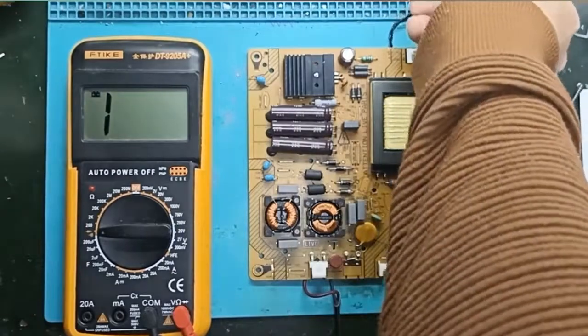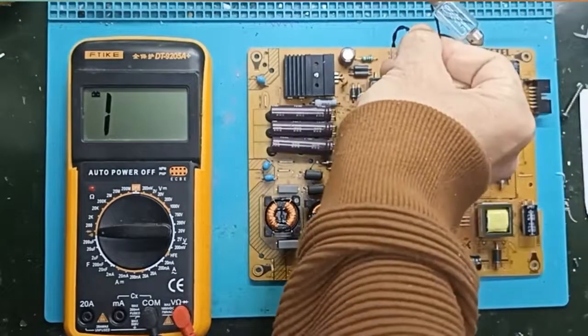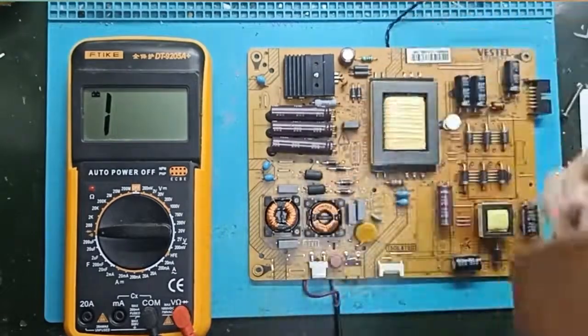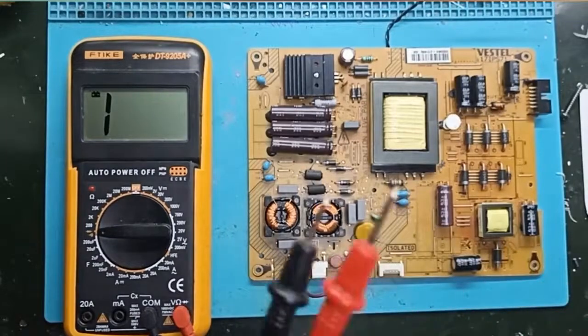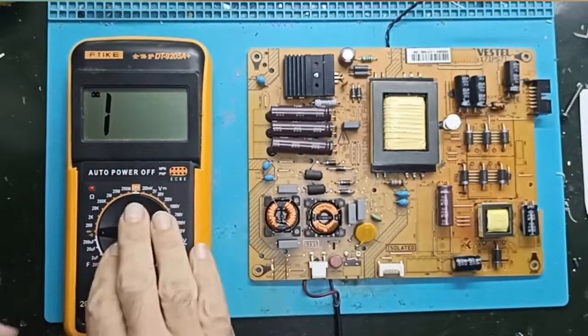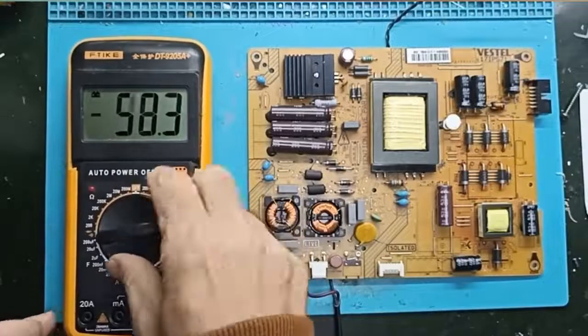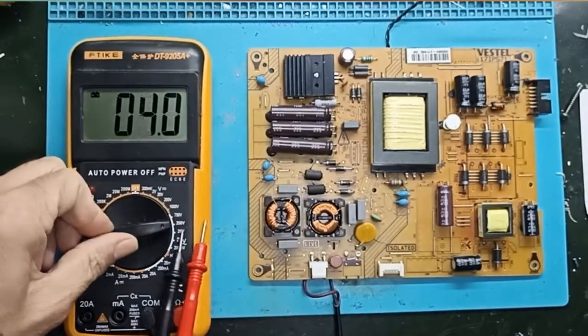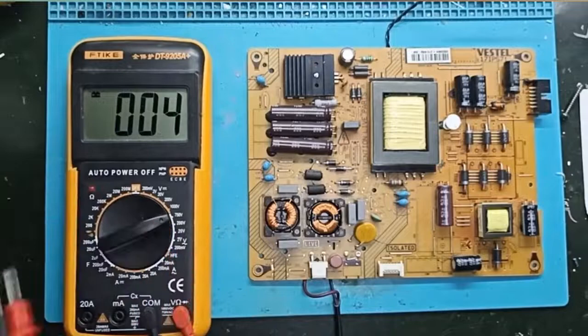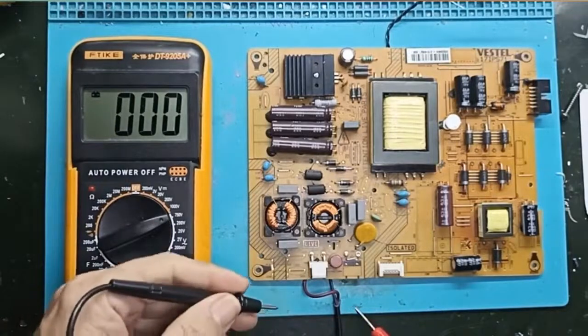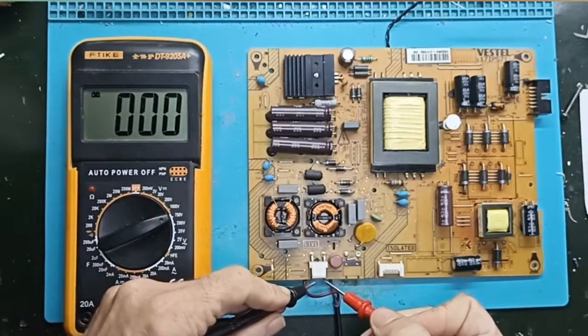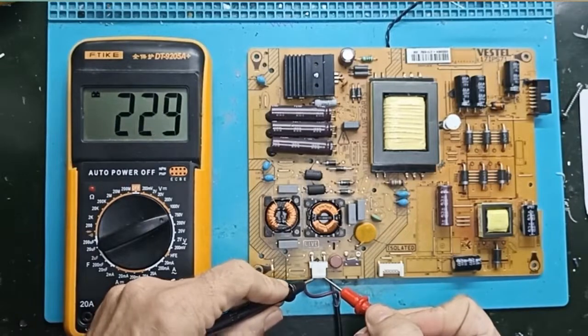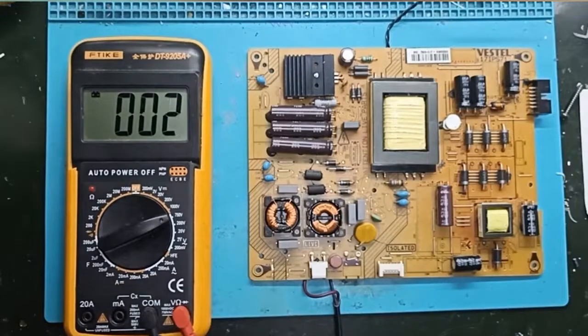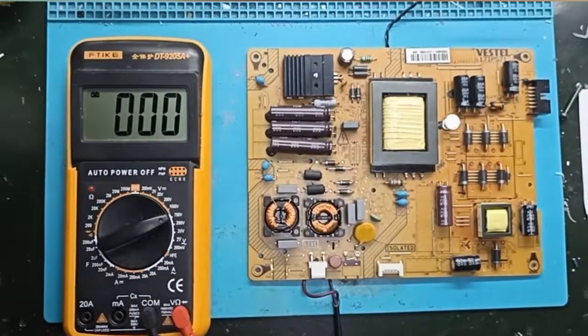You see the bulb here? It's burnt out. And what will we do now? First thing we will do is to measure the 220 volts with our multimeter, if they come to the entrance. Let's go for a measurement, and I measure directly at the entrance where the cable is. I measure here and see that I have 230 volts. So the voltage is coming from the network to the board.